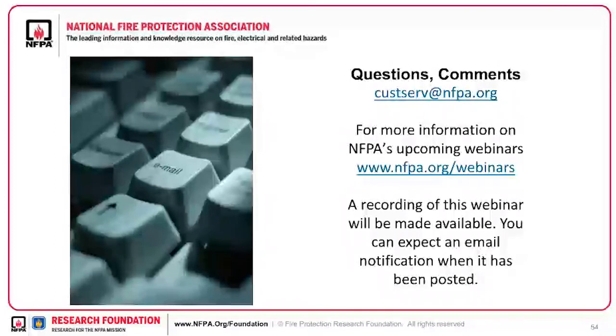Okay, next question. Does this mean that 13 feet of separation between module trailers is sufficient to prevent a cascading spread of fire? All right, so the 13-foot separation number is specific to the NMC test rack that we tested. FM Global's datasheet 5-33 recommends for an unknown system a separation of 20 feet. And that's sort of a general number when you don't know exactly what you're burning or how much energy capacity the system has, what the trailer looks like, whether it has venting. When you have all these unknowns in there, a conservative number that we use is 20 feet.